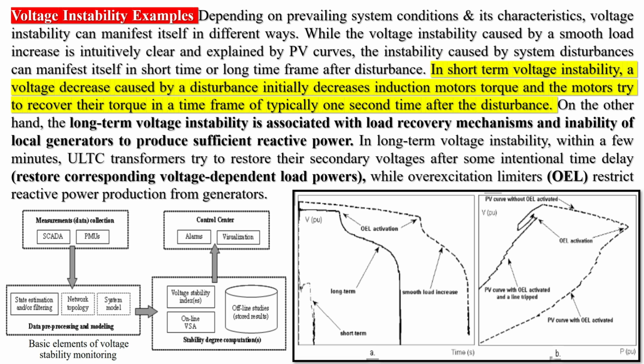While the voltage instability caused by a smooth load increase is intuitively clear and explained by PV curves, the instability caused by system disturbances can manifest itself in short time or long time frame after disturbance. In short-term voltage instability, a voltage decrease caused by a disturbance initially decreases induction motors' torque and the motors try to recover their torque in a time frame of typically 1 second after the disturbance.